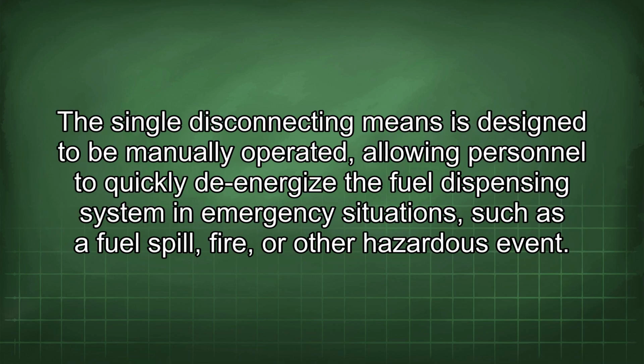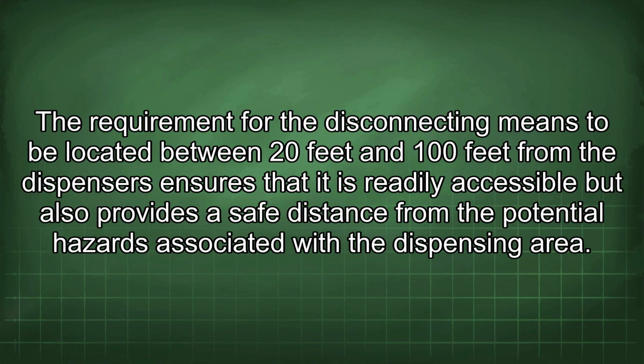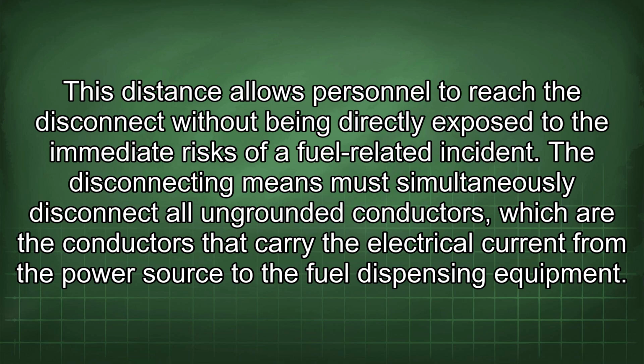The single disconnecting means is designed to be manually operated, allowing personnel to quickly de-energize the fuel dispensing system in emergency situations, such as a fuel spill, fire, or other hazardous event. The requirement for the disconnecting means to be located between 20 feet and 100 feet from the dispensers ensures that it is readily accessible, but also provides a safe distance from the potential hazards associated with the dispensing area. This distance allows personnel to reach the disconnect without being directly exposed to the immediate risks of a fuel-related incident.